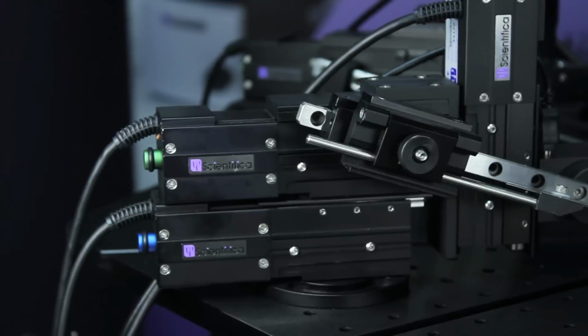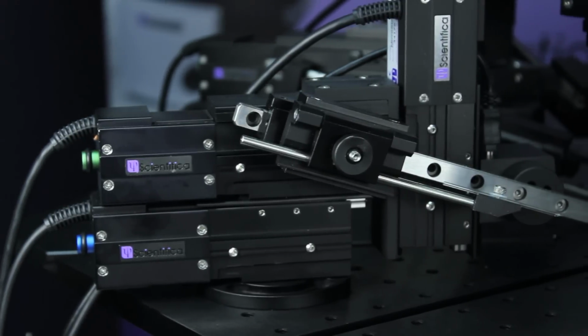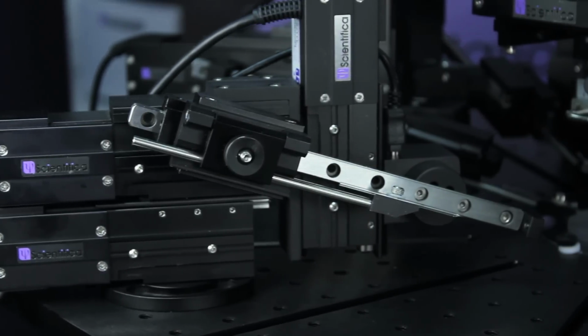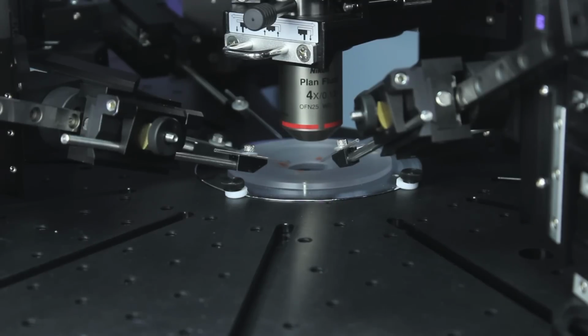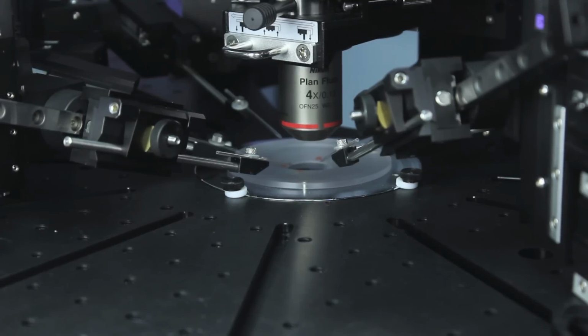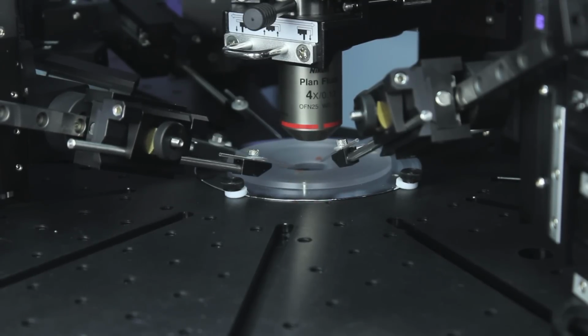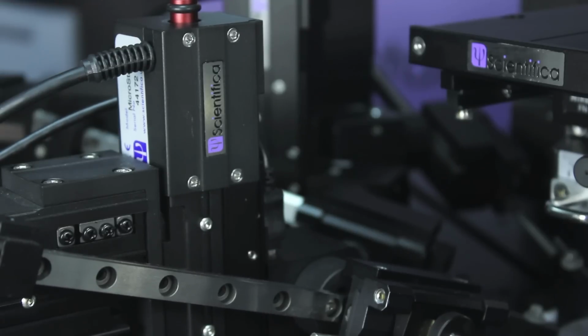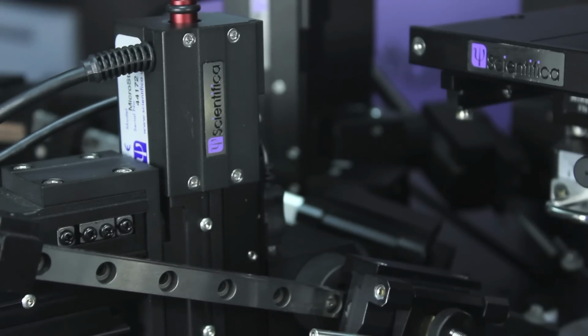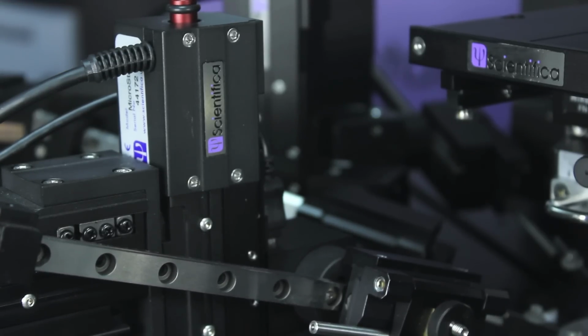From the same family as the PatchStar Micromanipulator, it also has 4 axes of movement, X, Y, Z, and a virtual approach axis. With 20 nanometers resolution, it offers 20 millimeters smooth travel in X and Z, and 14 millimeters in the Y axis, allowing you to easily patch any part of your sample.